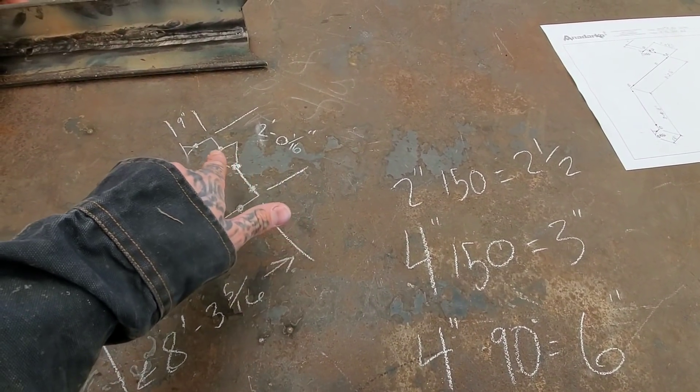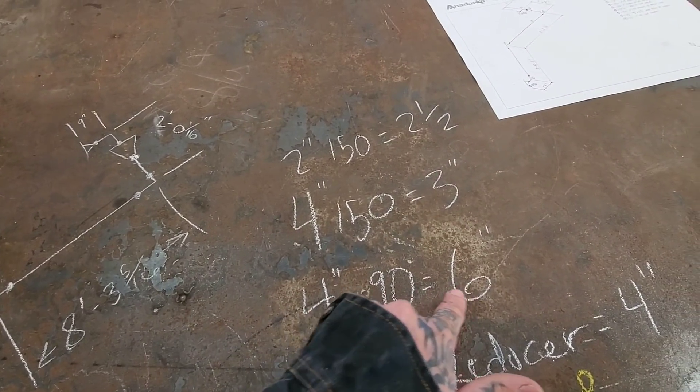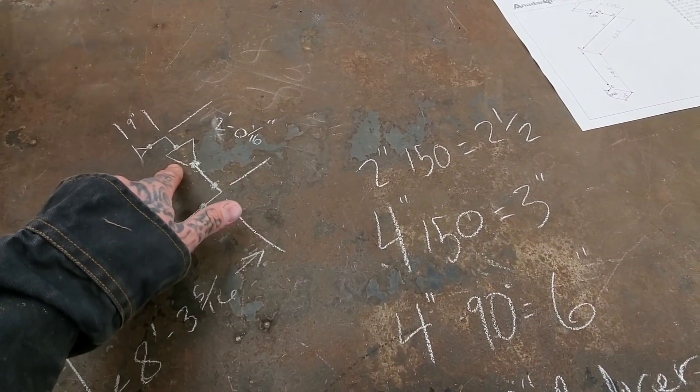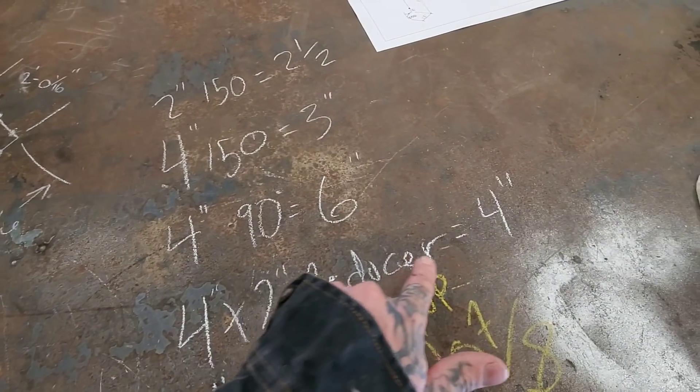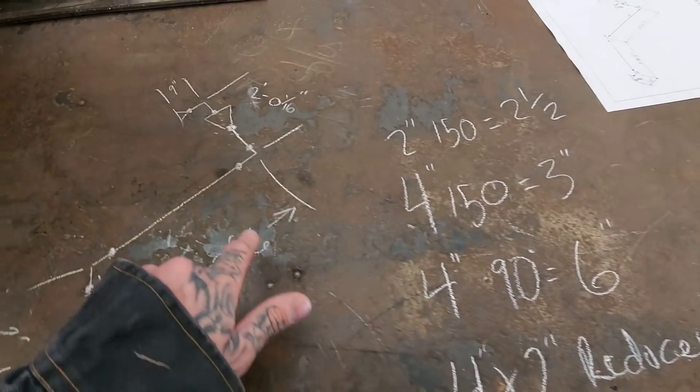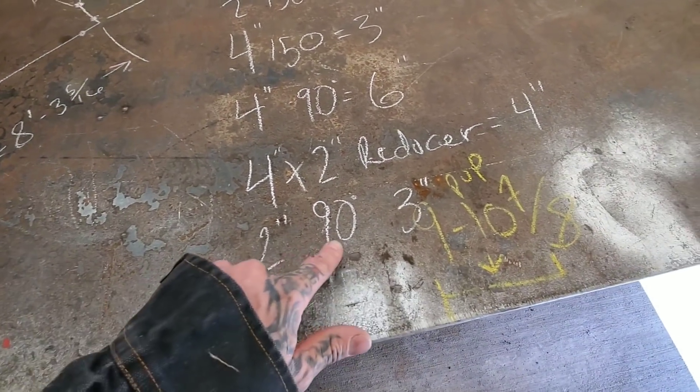Next up is a four inch long radius 90 which is six inches in my blue book. Now remember I said long radius. This is a four by two reducer and in my book it says that it equals four inches. Next up is a two inch 90, the two inch long radius 90 is three inches.